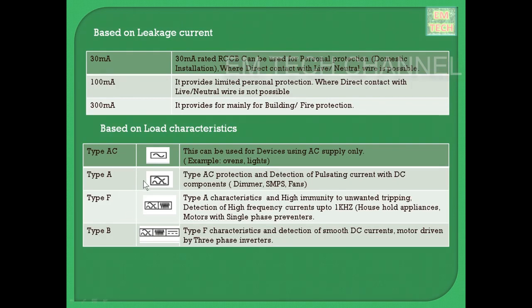Next, the type F RCCB. As seen in the previous case, it combines the function of type A RCCB also, and in addition it provides high immunity to unwanted tripping and detection of high frequency currents up to 1 kHz. These RCCBs are mainly used in household appliances, motors with single phase preventers, etc. It can be seen through this symbol. You can see here this symbol is type AC, type A, and it is a unique symbol for the type F RCCB. Okay, so next comes type B RCCB.